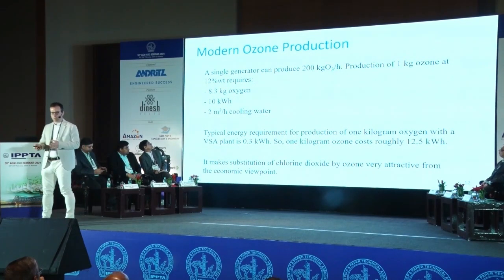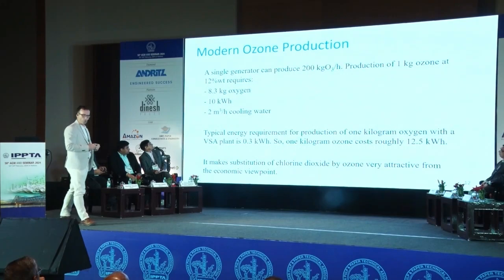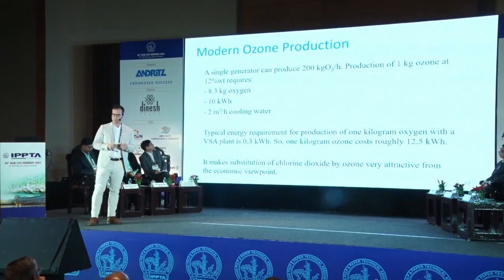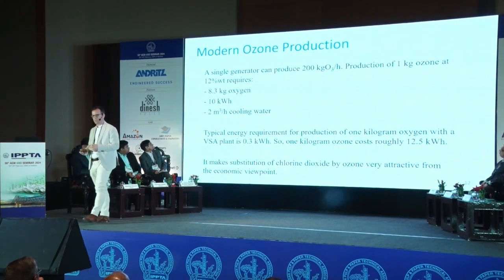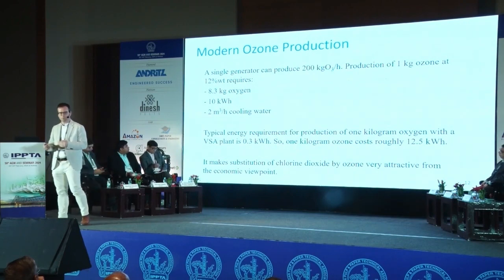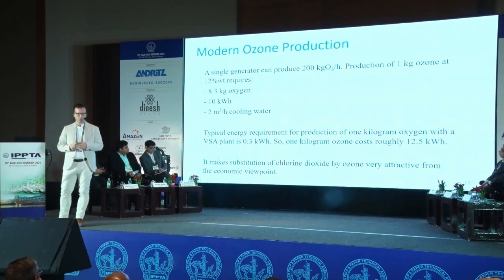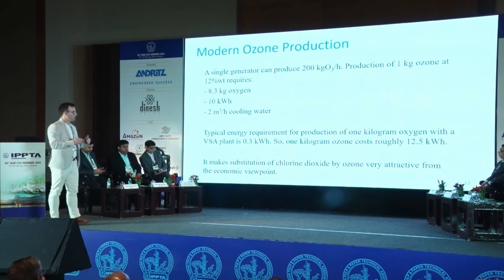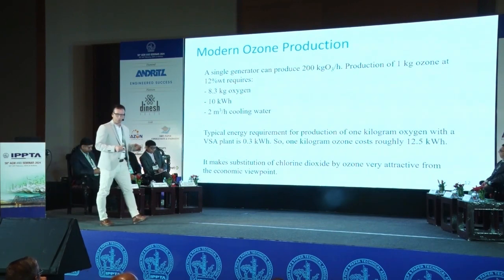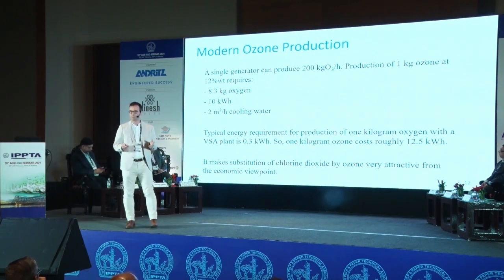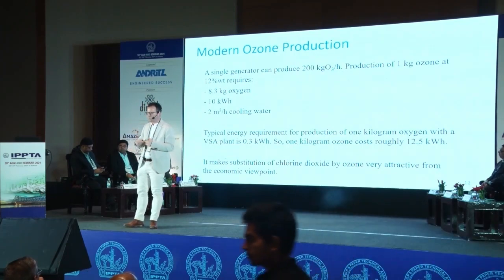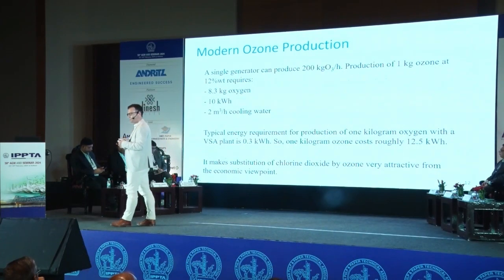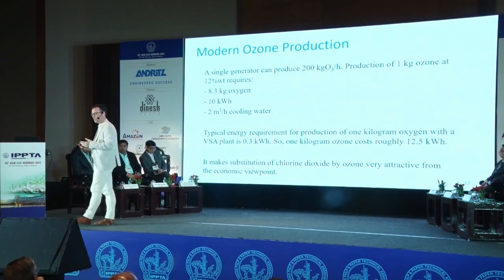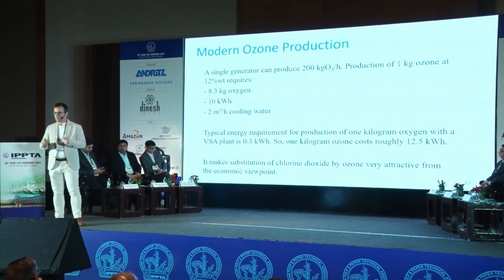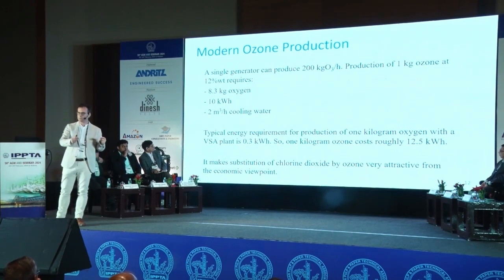So to produce 1 kilogram ozone at 12% by weight in oxygen, we need 8.3 kilogram oxygen, 10 kilowatt, and less than 2 cubic meter of cooling water. Oxygen being produced at site, if we consider how much energy is needed to produce oxygen, altogether, the 1 kilogram ozone needs 12.5 kilowatt. If you know the cost of your electricity, then you know the cost of ozone at your location.